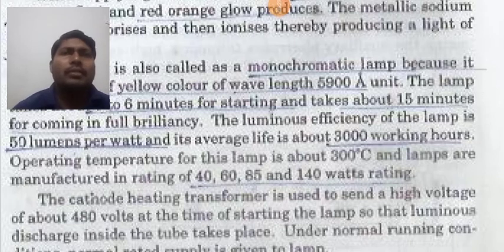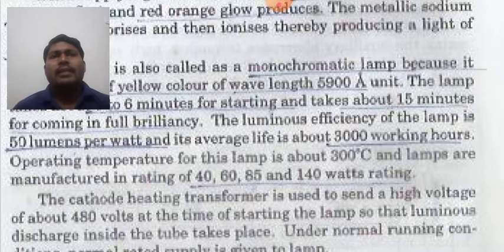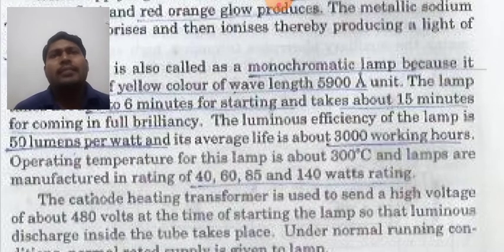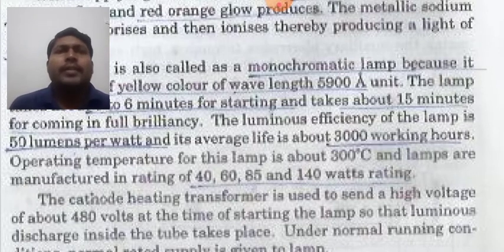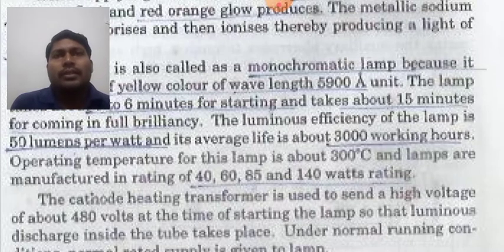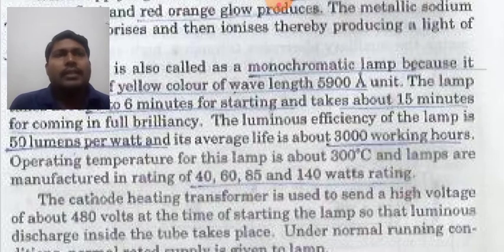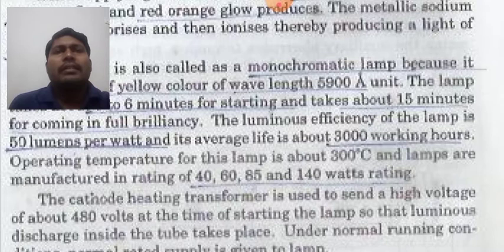The operating temperature of this lamp is about 300 degrees centigrade and lamps are manufactured in ratings of 40, 60, 85, and 140 watts. You can choose a particular wattage according to your requirement. The cathode heating transformer is used to send a high voltage of about 480 volts during starting, so that luminous discharge inside the tube takes place.